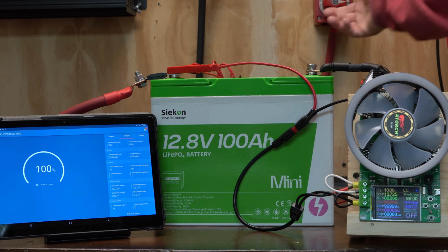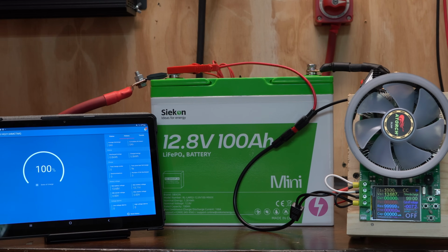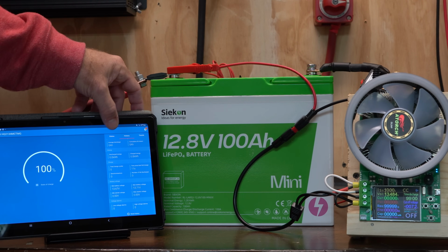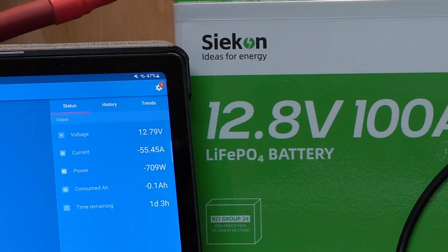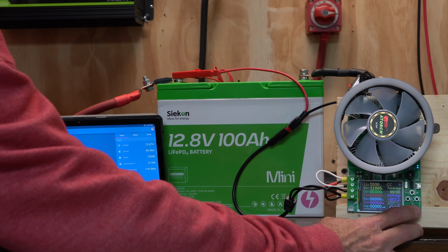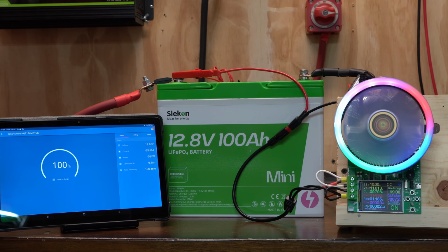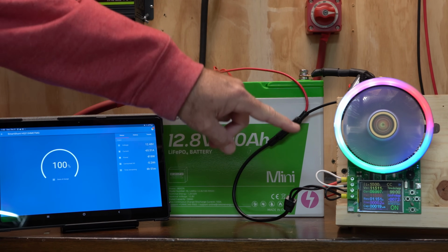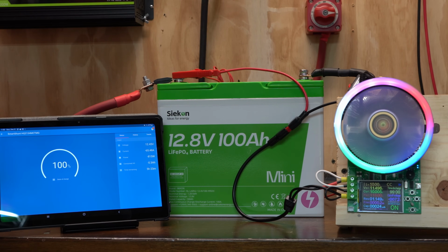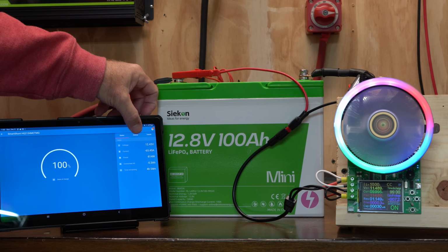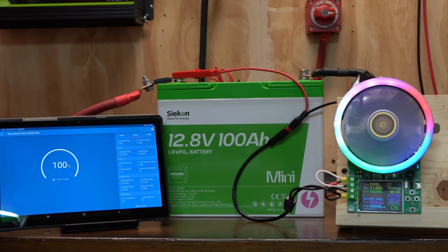Go ahead and apply a load. I've got my smart shunt hooked up to this. We are pulling 55 amps. Let's go ahead and run the DC tester as well, so that when the AC inverter shuts off due to low voltage before the BMS does, this will finish it out and we'll be able to capture all of the amp hours we were able to get out of this battery before the BMS kills it.